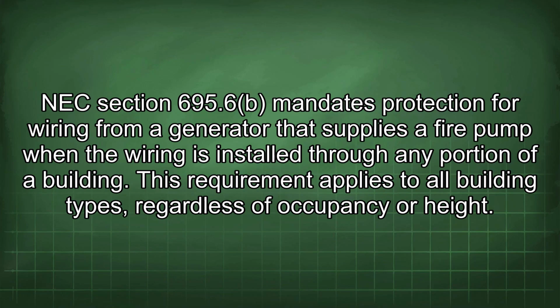NEC section 695.6 mandates protection for wiring from a generator that supplies a fire pump when the wiring is installed through any portion of a building. This requirement applies to all building types, regardless of occupancy or height.